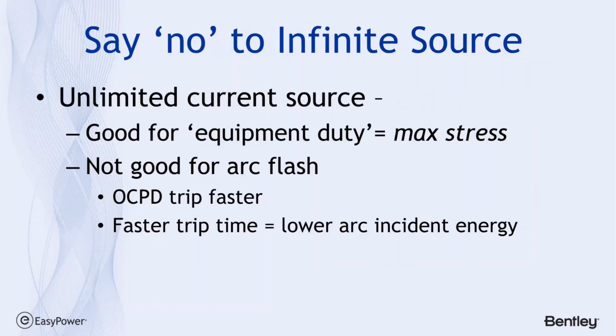But in any case, you don't want to use an infinite source. And I say that because an infinite source has its purpose. For instance, calculating equipment duty on a worst case situation, but it's not good for arc flash. And the reason for that is that it trips faster. The protective devices trip faster, and consequently we get a lower incident energy, which is not being conservative.